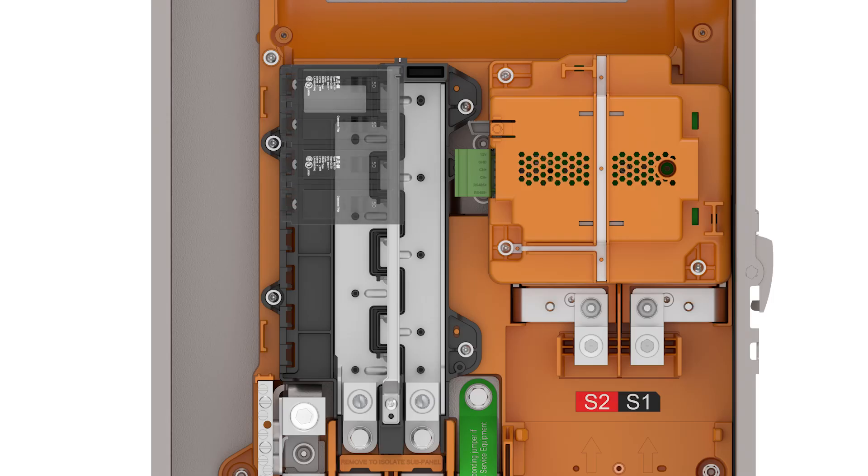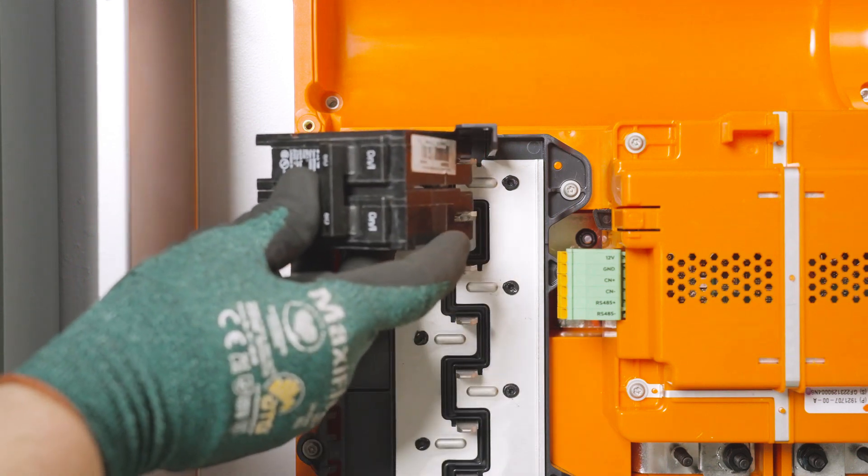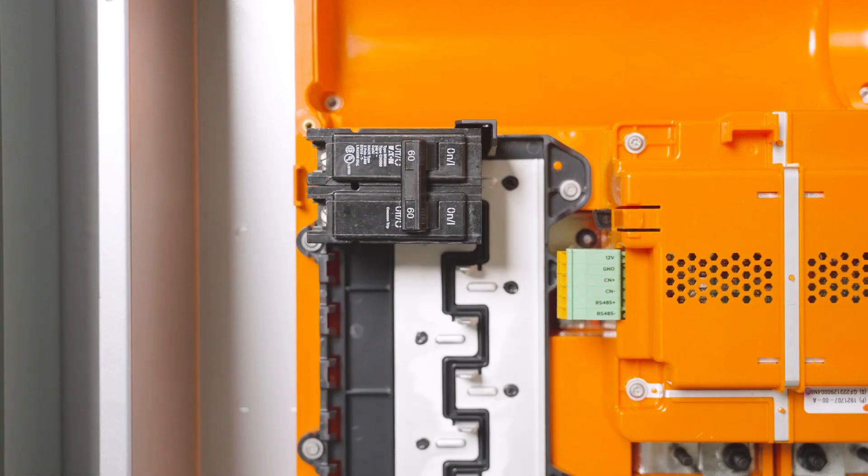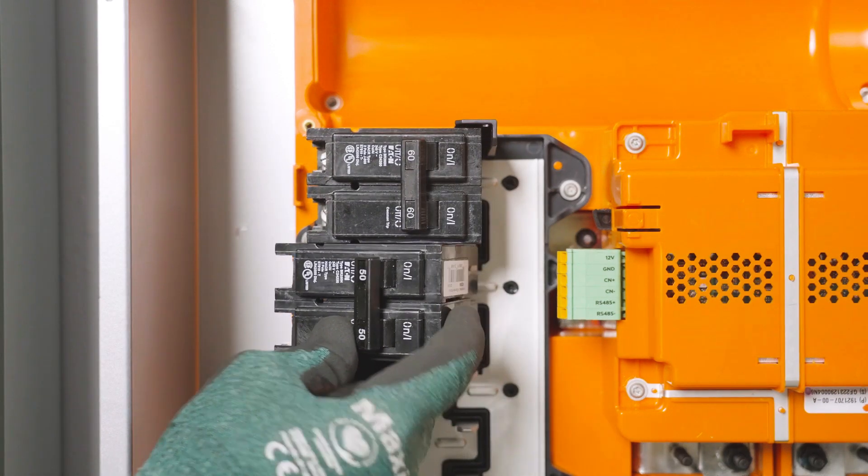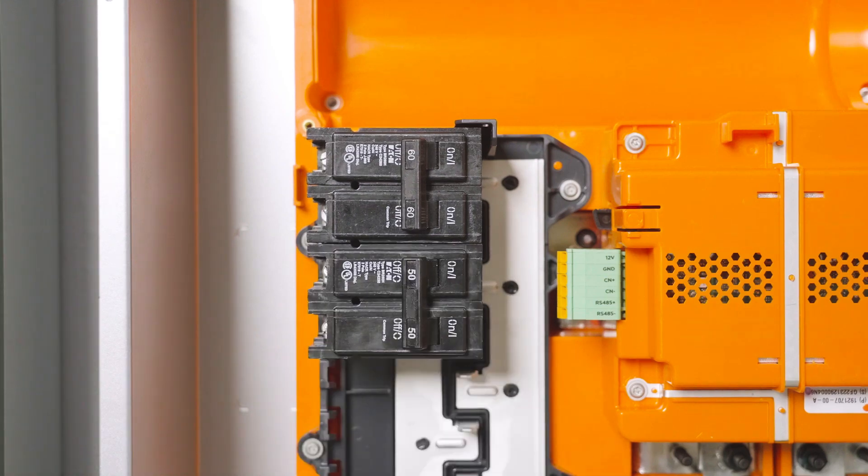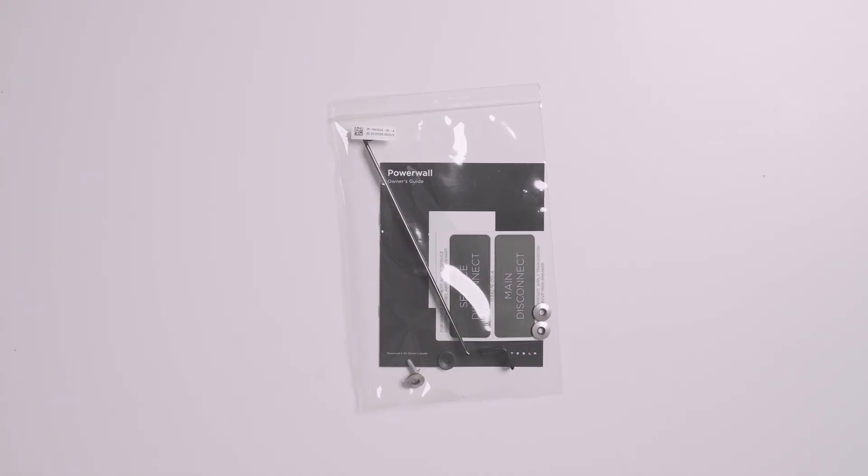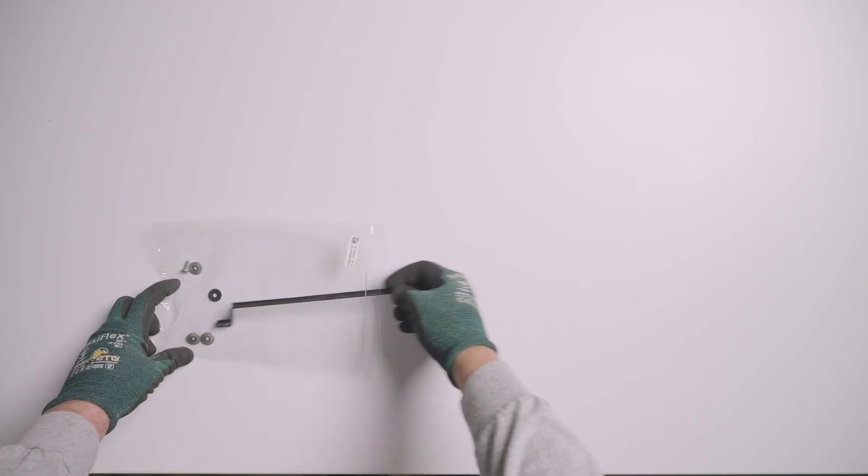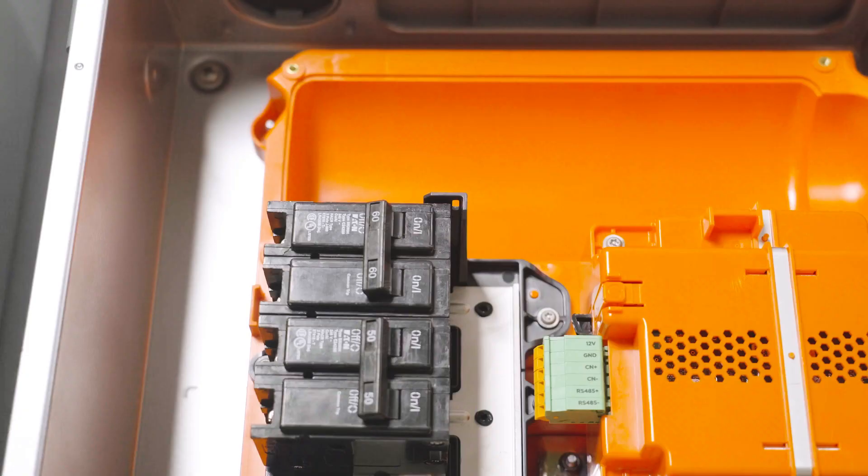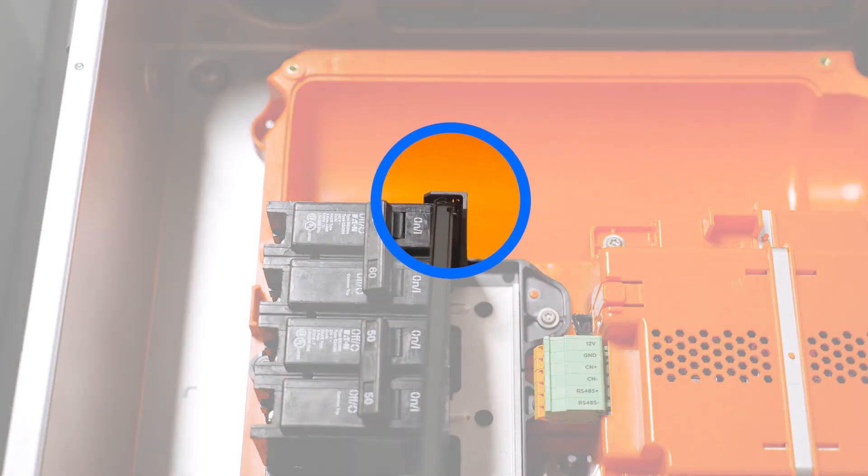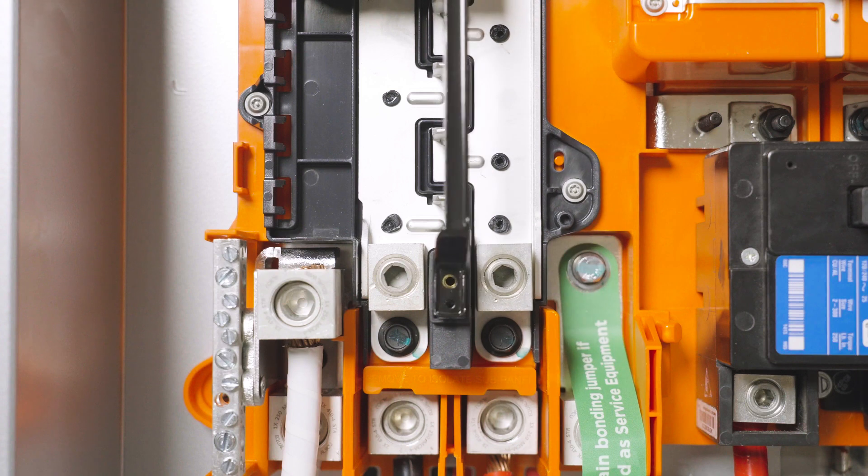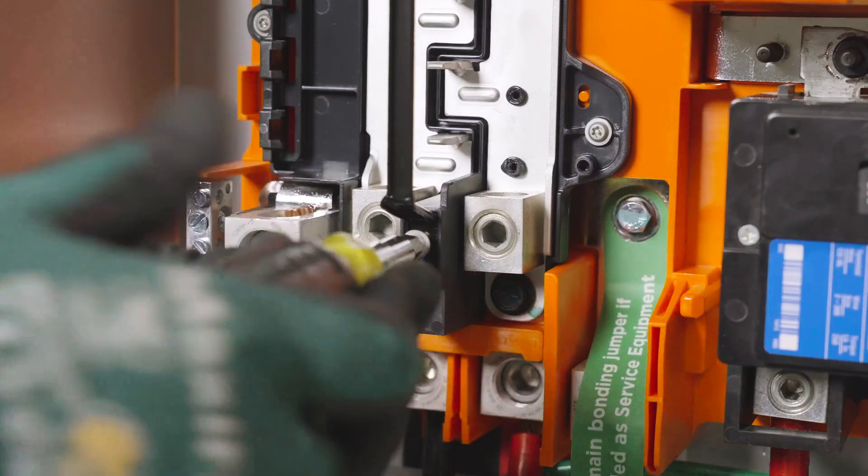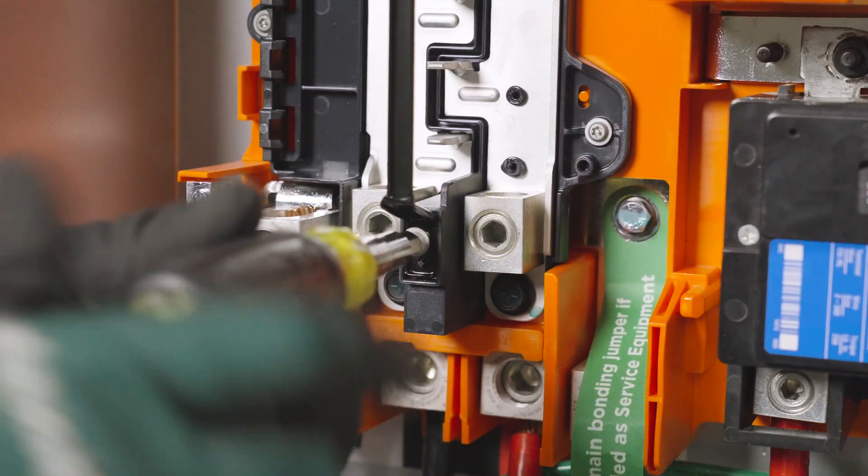To install a breaker onto the internal panel board, engage the tab of the breaker onto the left side of the panel, then rotate the breaker contacts onto the bussing. After all breakers are installed, secure them with the hold down bracket included in the accessory kit. Begin by inserting the top of the bracket into this opening above the internal panel board. Fasten the bottom of the hold down bracket using the T20 Torx screw provided in the accessory bag.